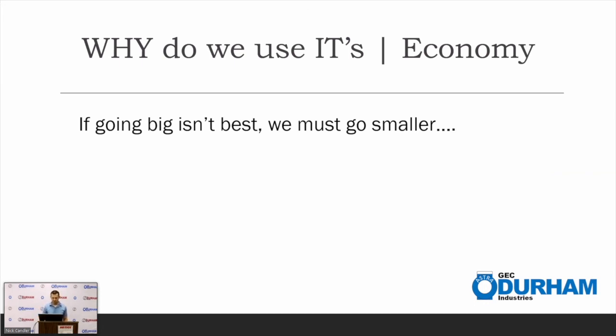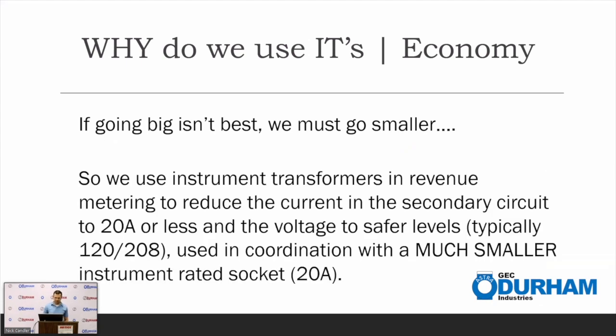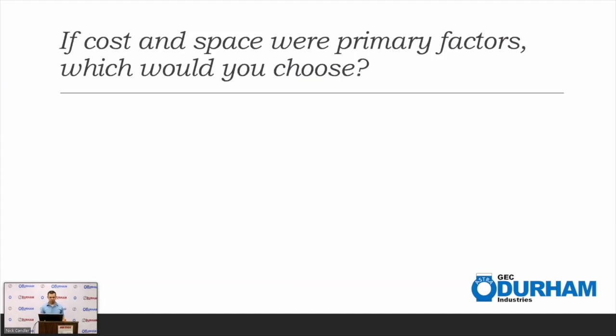And we use instrument transformers to do that. We're going to reduce the current down to 20 amps or less. And in some uses, utilities will use the voltage transformers as well to get the voltage down to 120, 208. And we use a 20 amp socket to do that. So much smaller. If cost and space were primary factors, which one would you choose?